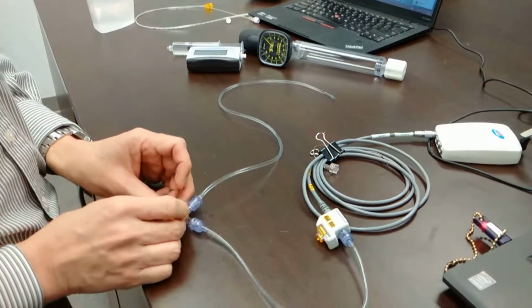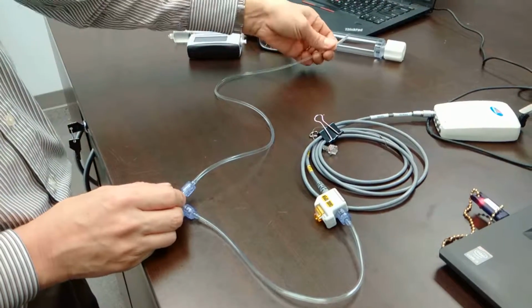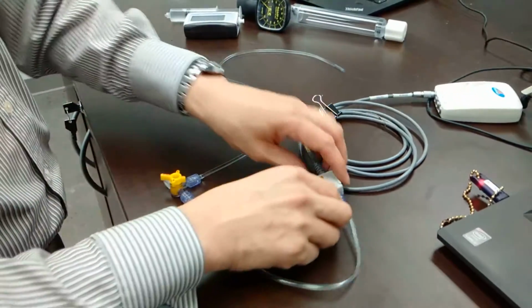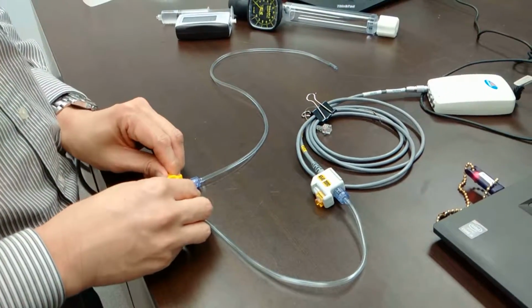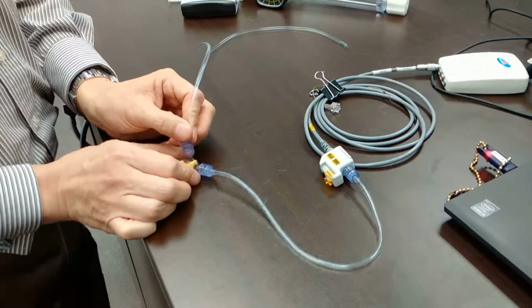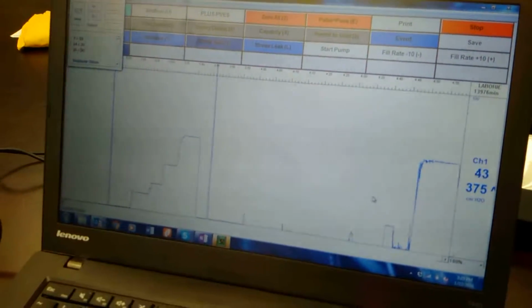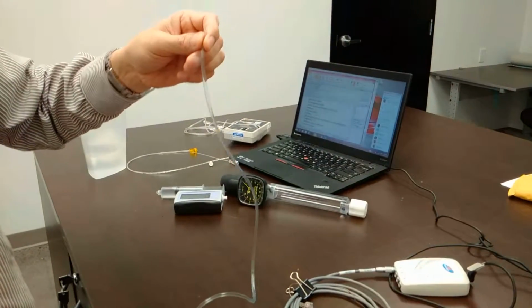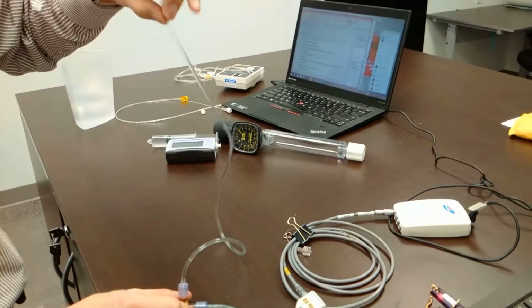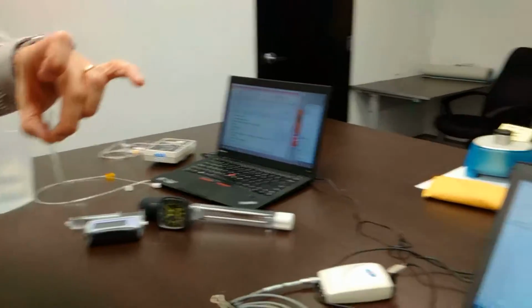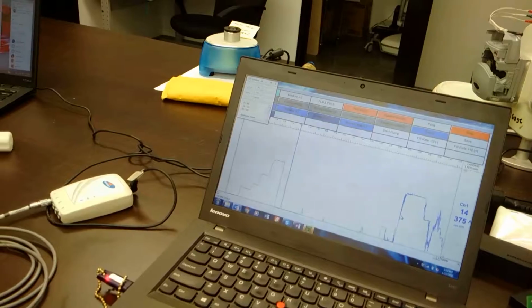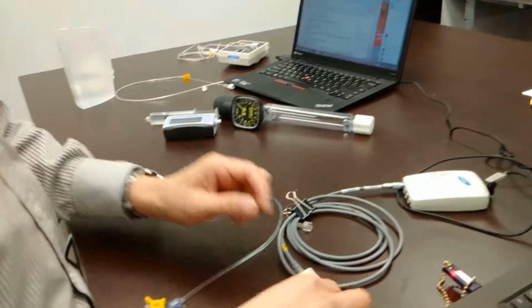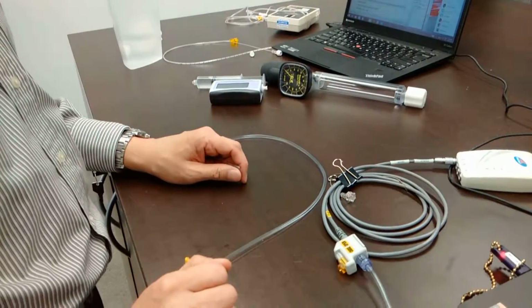So this section is only air, and we prime the system with a syringe so there's only water in here. So what we do is we charge it, and now we turn it like this. Now we have to use a tape measure. But essentially, you will see when I raise it up here, it's not quite, it says 59 centimeters. And if I lower the tubing, notice that the pressure values go down. So if I had a tape measure that measures from the stopcock to the level of the tube, that's going to give me the different pressures that I want to measure. Okay, so that's a very inexpensive way to validate that the pressures are working correctly.